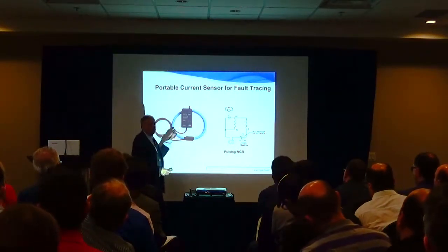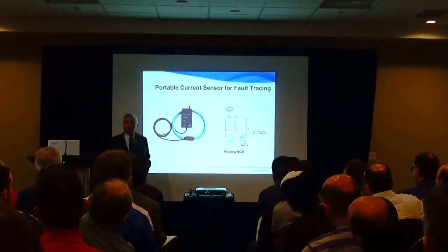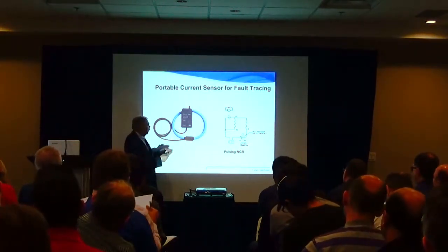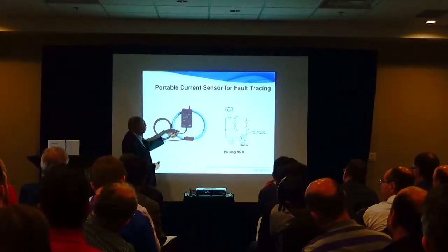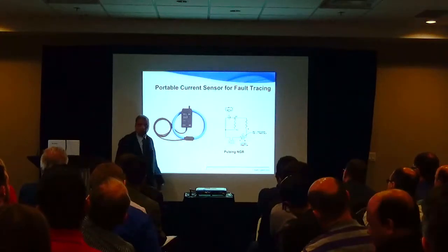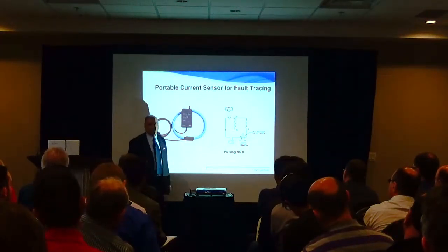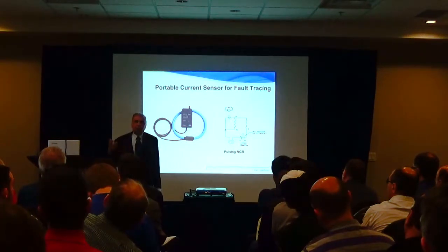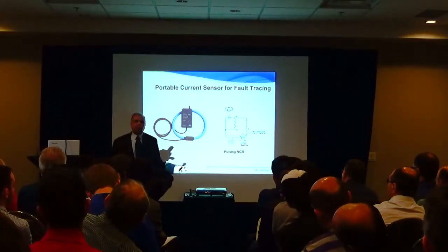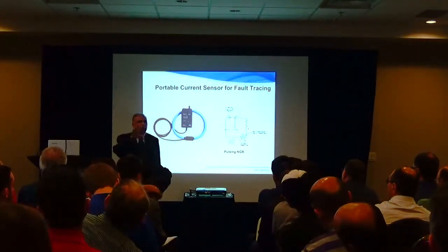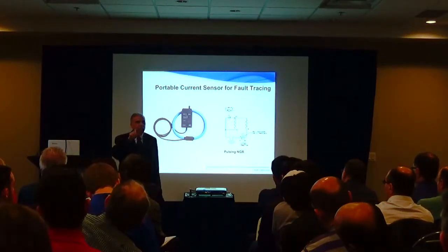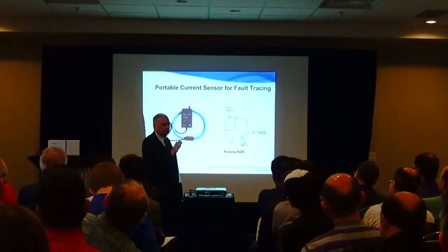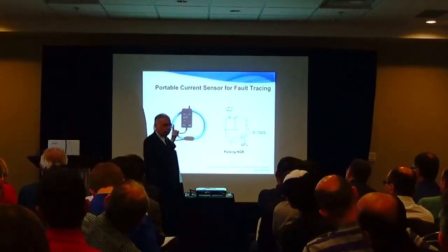This is an accessory that should be kept where the high resistance grounding system is, so that when the time comes, they can go to it and locate the fault. The clip allows you to go outside the bonding conductor. The signal from the sensor is normalized to a 100 millivolt AC scale, and the multimeter gets plugged into this so that you are on a 100 millivolt AC scale looking for that oscillation. You're not measuring current because you are outside the bonding conductor. The current will find all possible return paths through the bonding conductor back to the transformer. So you are only looking at the change pattern. It distinguishes from the noise. The noise will be eliminated because you have a set pattern for change of the resistor value. So you are looking for that needle shifting periodically to your frequency.